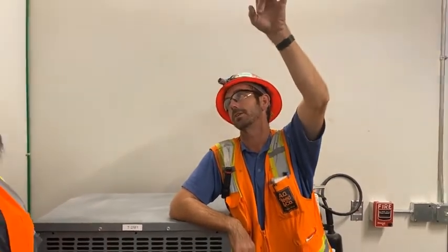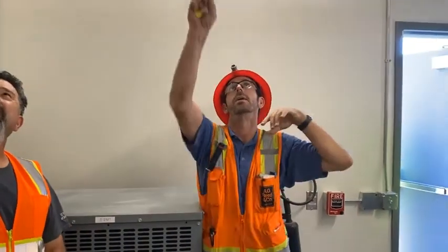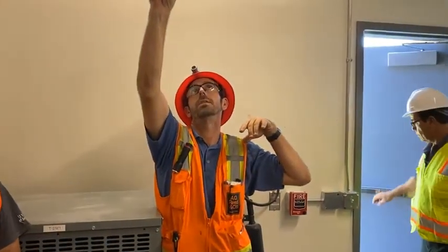The only difference there, we don't have a 3-way valve. Since this is the farthest run on chilled water, this is the only 3-way. Oh, we're not supposed to have 3-way valves either. This is a 3-way. Because we get charged by the BTUs, so if we're bypassing it, we're picking up something. Yes, potentially. But because all our buildings are tied to the same system, we all have 2-way valves. That way when it opens, it feeds; when it closes, there's no flow, there's no charge for BTUs.